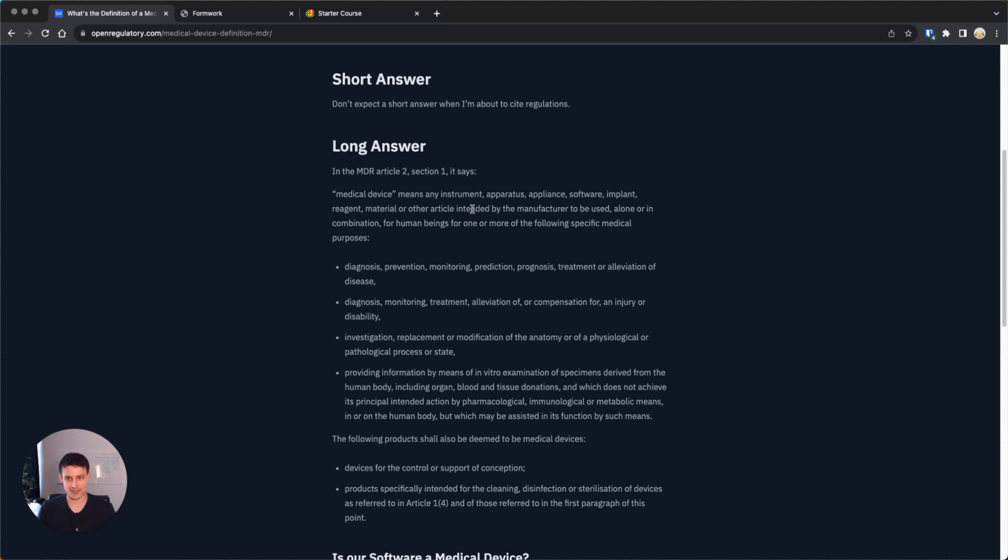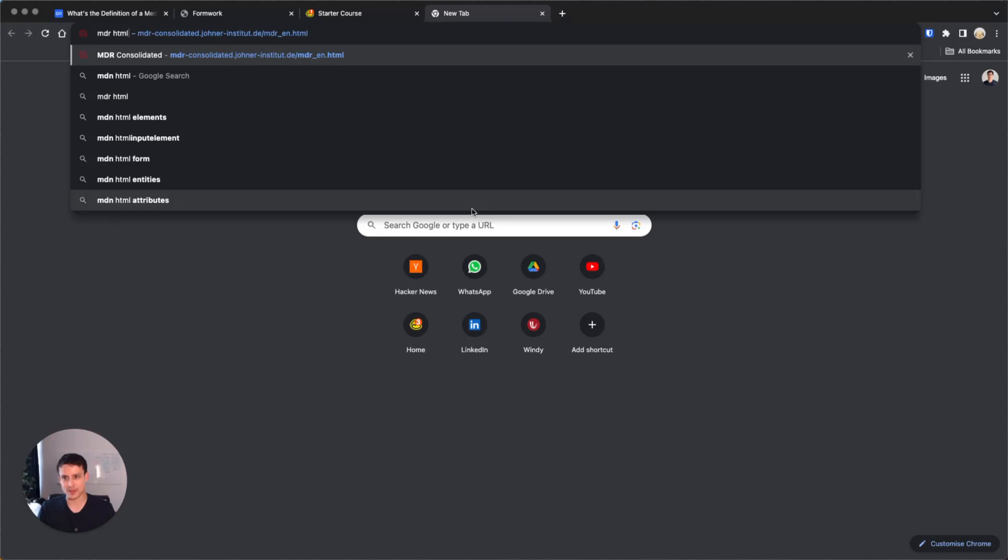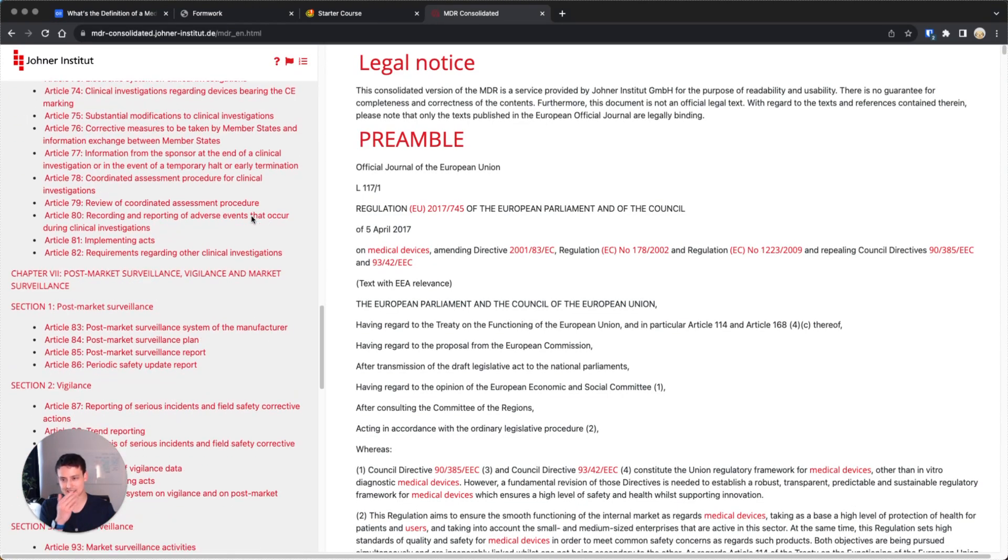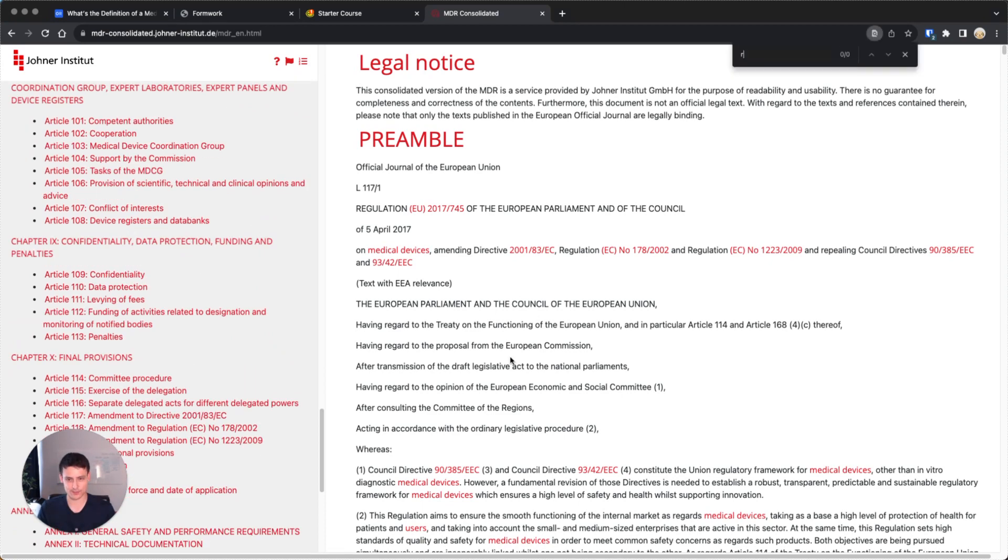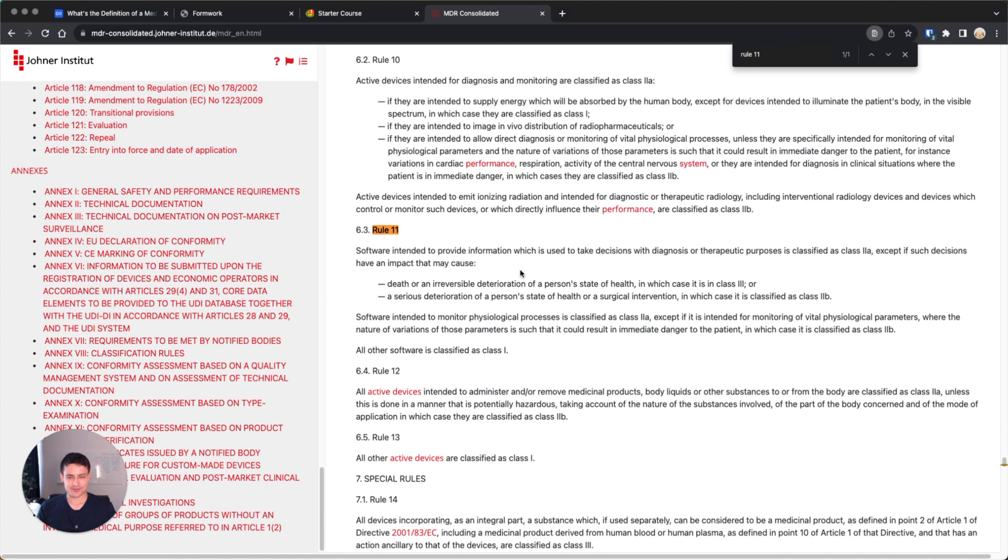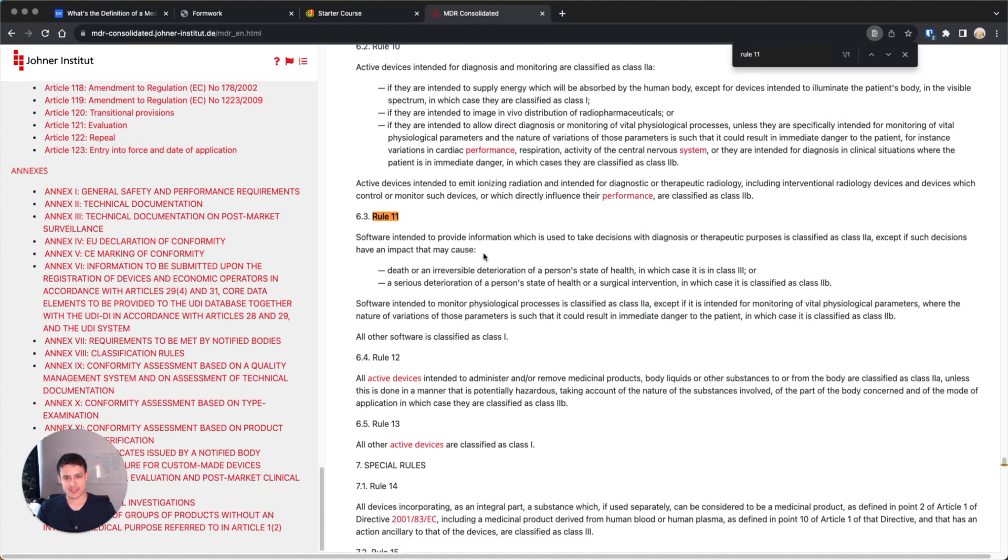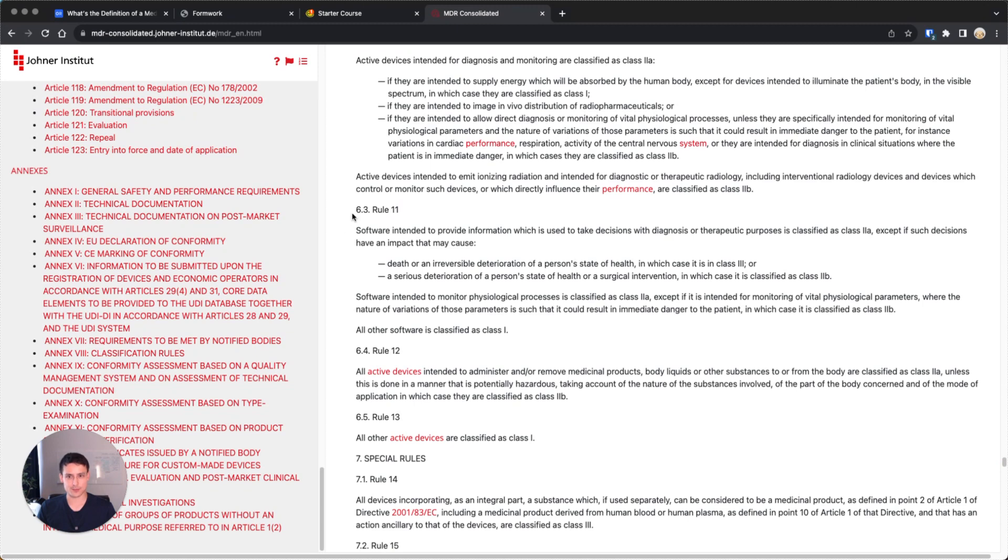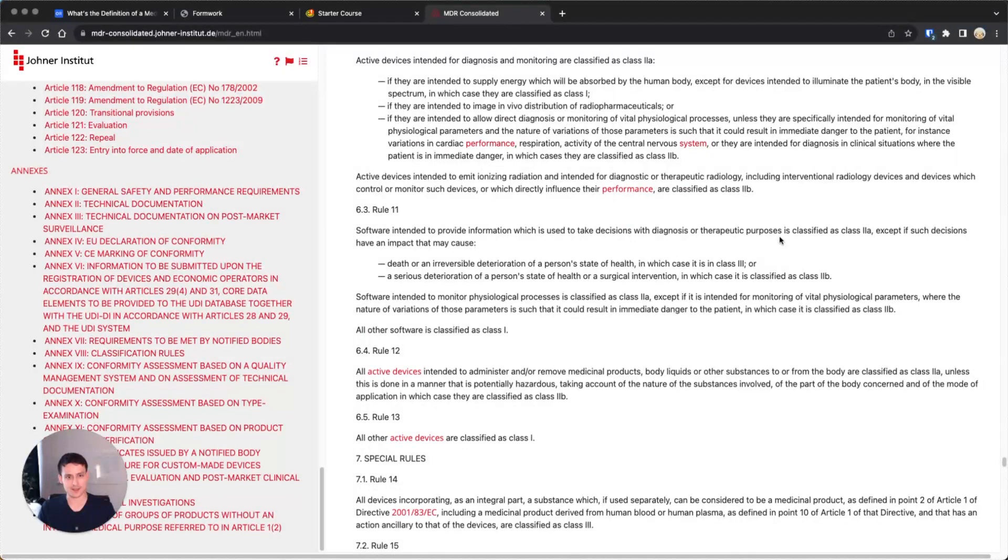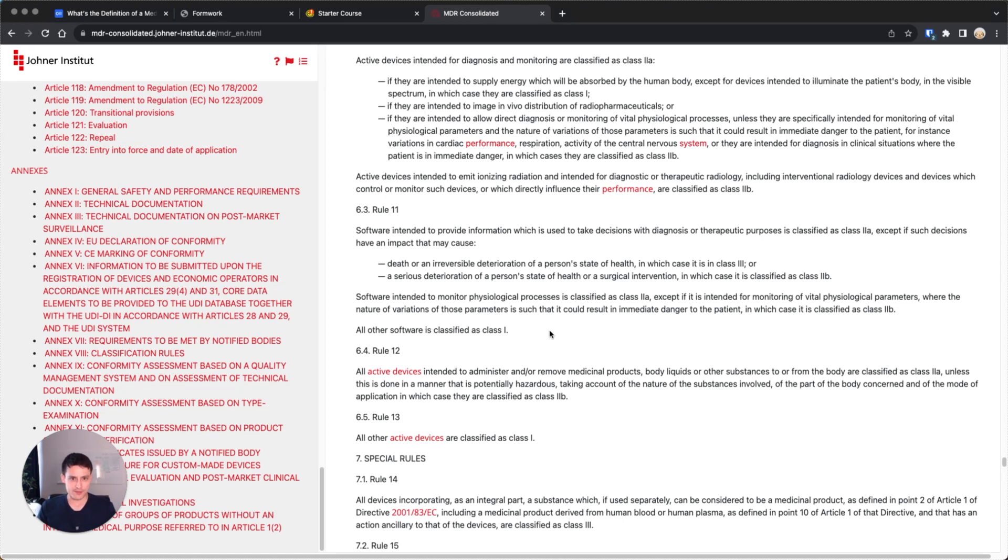The big question is, are you a class 1 device or not? Let me actually go to our competitors. Well, they're actually nice people. They uploaded the MDR as HTML, which I think is super useful. The main thing influencing whether you're class 1 device or not will be this Rule 11. I'm going to skip ahead over many things here. Generally, it says software intended to provide information which is used to take decisions with diagnosis or therapeutic purposes is classified as class 2a.